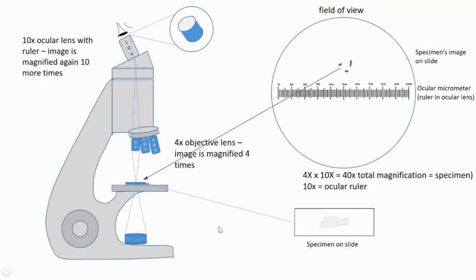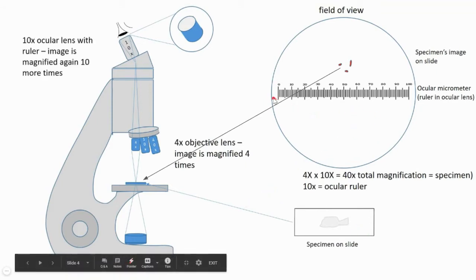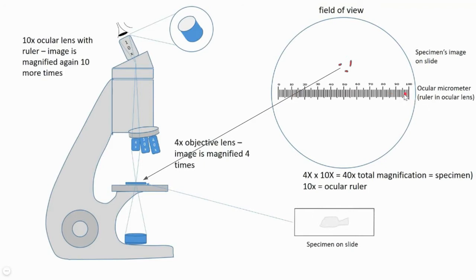You will notice that the ocular micrometer does not have any units. There are large divisions, medium-sized divisions, and the smallest divisions in between. Counting every gap gives a total of 100 divisions on this ocular micrometer. However, you do not know the length of this scale — that is why we say it is uncalibrated: you only know the number of divisions but not the actual length of the scale.